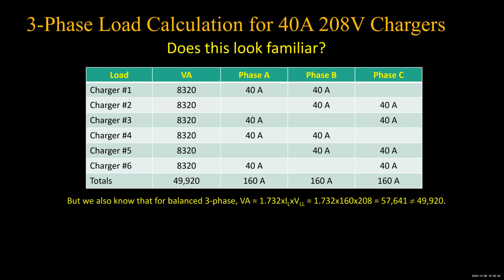So, except for one little thing, for a balanced 3-phase load, and this is certainly a balanced 3-phase load, line to line, the volt amps is 1.732 times line current times line voltage, to 57,641. And we only got 49,920. What happened to the extra 8,000 watts or so, or 8,000 volt amperes? Wow. Now that's an interesting thing, by the way. This says volt amperes, not watts.